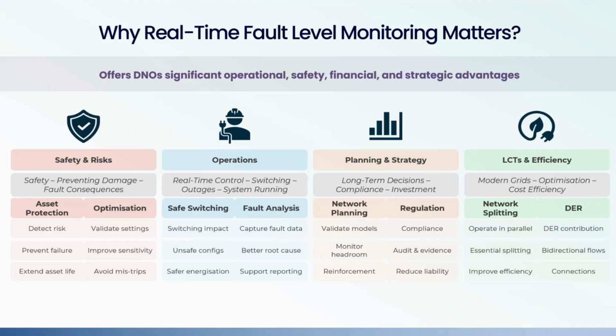Operationally, however, fault level changes every time the network is reconfigured, during switching, restoration, or normal system running. Real-time monitoring allows the control room operators to see the fault impact before switching, which means avoiding unsafe configuration and enabling safe energization even in close onto fault situations. And when the fault occurs, that same data is already captured. So it gives us accurate pre-fault and during fault records to support better root cause analysis and reporting.